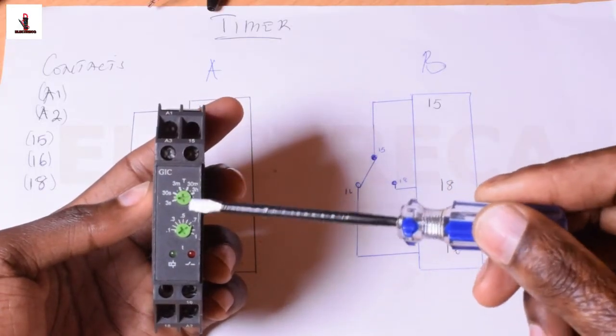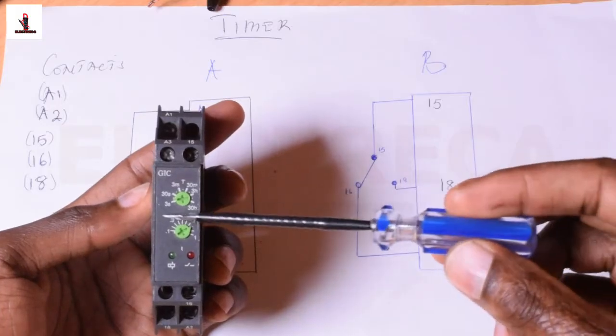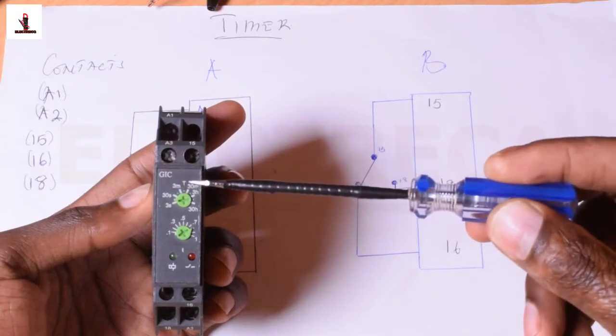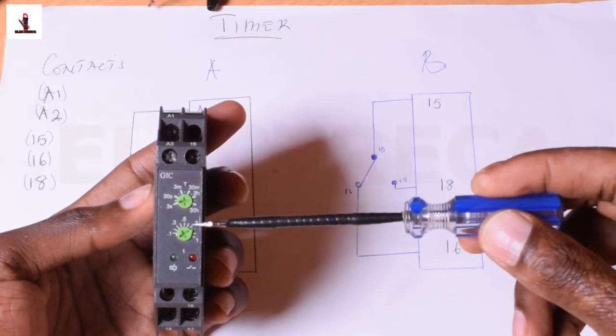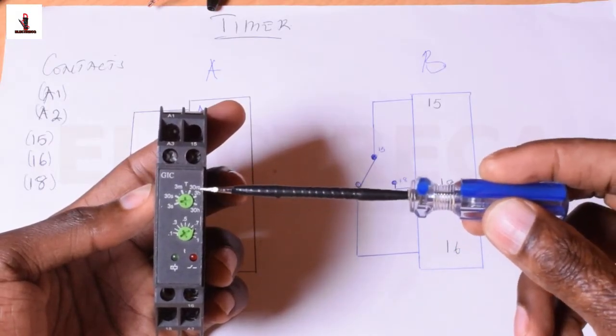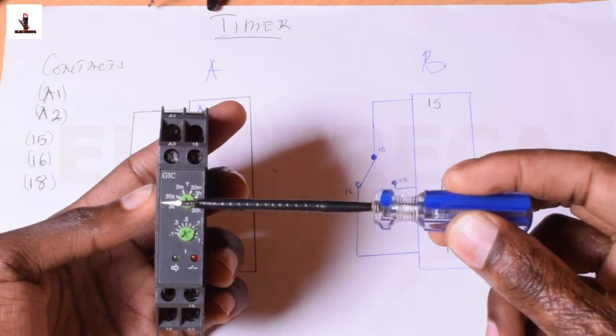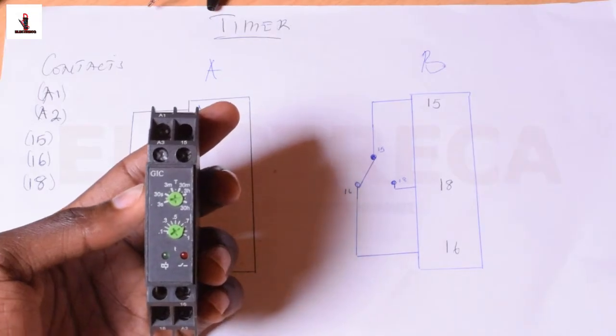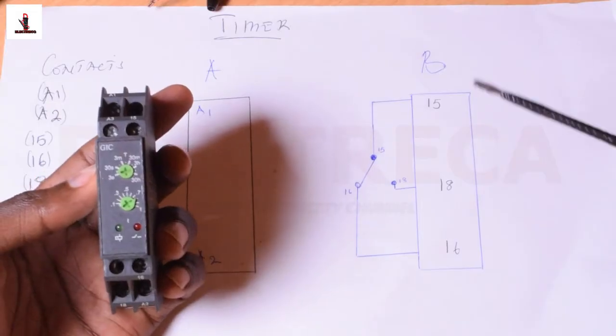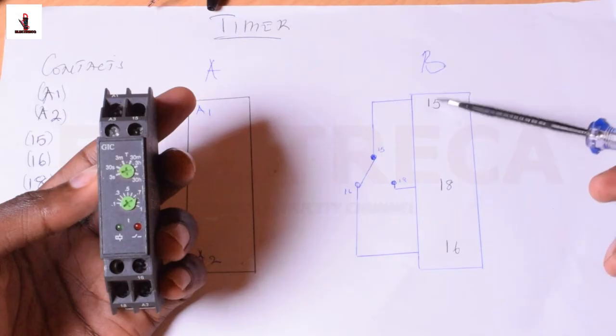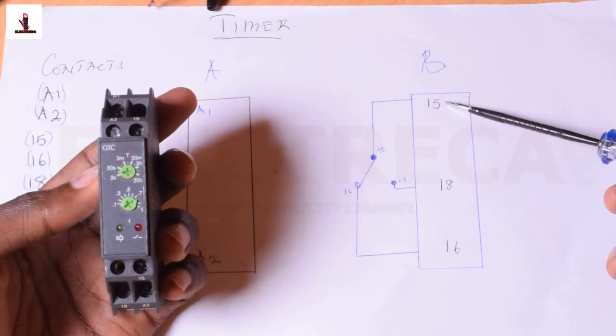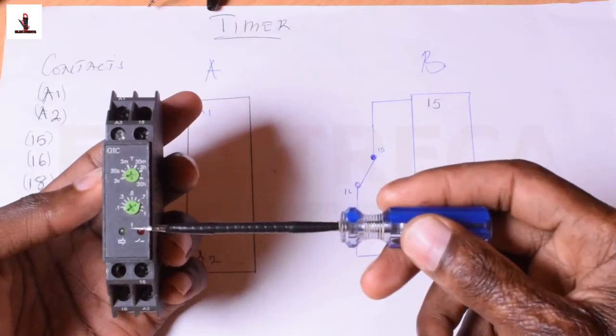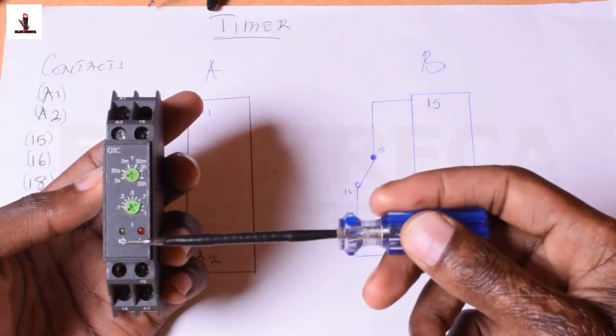You see it has got a dial, some two dials here. And here you have got time in seconds, time in minutes, time in hours. You have 30 hours, three hours, 30 minutes, three minutes, 30 seconds, and three seconds. Now that means that your time that you set—the moment because this is an on-delay timer.